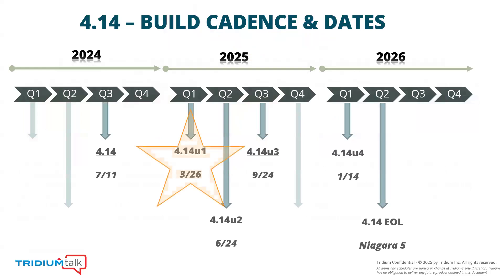Looking into the future with 4.14, we've got 4.14 U1 staged to come out at the end of next month, and it will continue until Niagara 5 is released, targeting 2026. One thing to call out about Niagara 4.14 is that this is the last version that will support Wi-Fi on the JACE 8000. Coming with 4.15, the 9000 — which is more powerful and Niagara 5 ready — is getting Wi-Fi support. So start thinking about that upgrade and working with your customers to move if Wi-Fi is critical on the 8000.